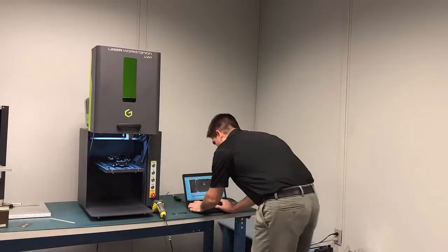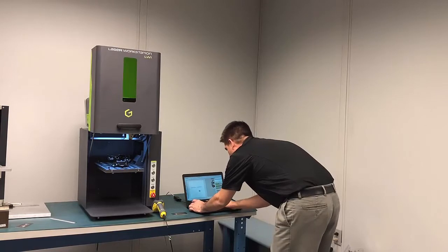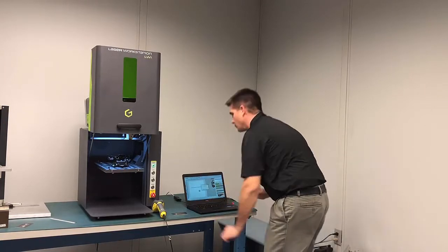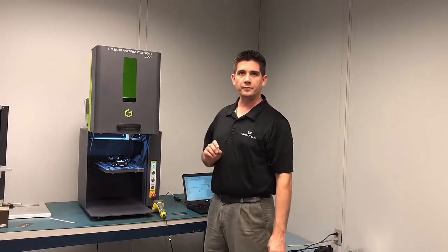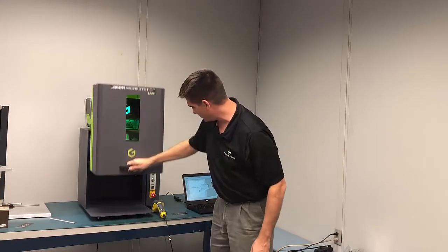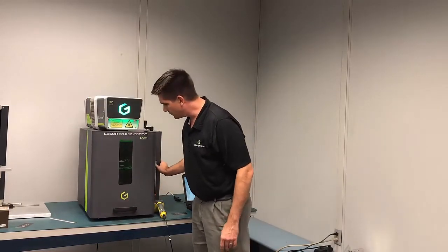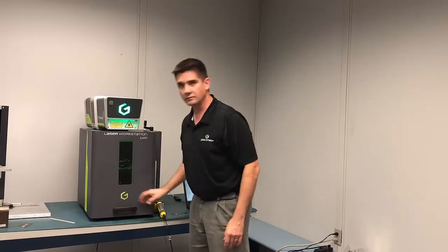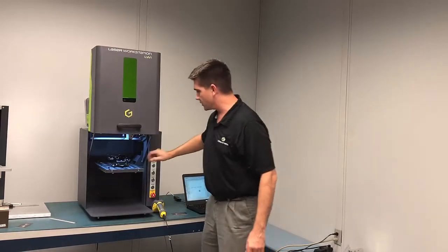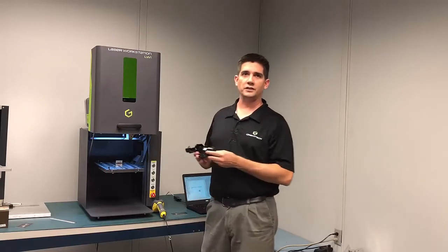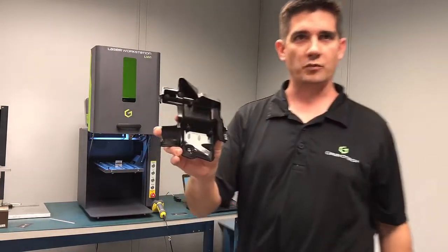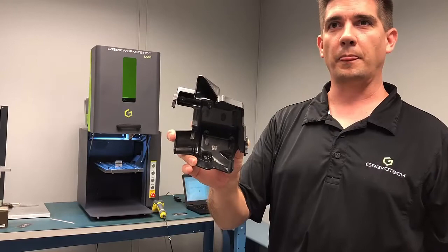We just need to center the first marking area under the autofocus center. Since our job has already been created with settings for plastic, we just need to send it over and then we can hit the button to fire the laser. You can really see the speed in which the laser applies the mark. The autofocus really helps in a situation where different size or shaped parts are being marked with the same laser.